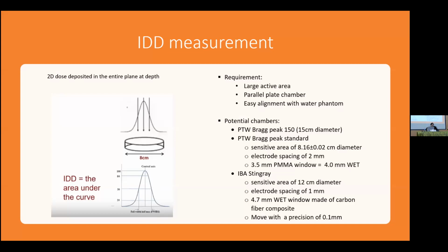An IDD means integrated depth dose. So this is maybe the only measurement you're going to do where, for a spot coming in water, you're going to try to measure what it looks like in depth. And what you want to be able to do is gather everything, be able to measure all the protons that are coming through at different depths. So you need a large detector for that. So you need a large active area, usually a parallel plate type chamber, and I'll show why in a bit. And you usually have to do this in a water phantom.